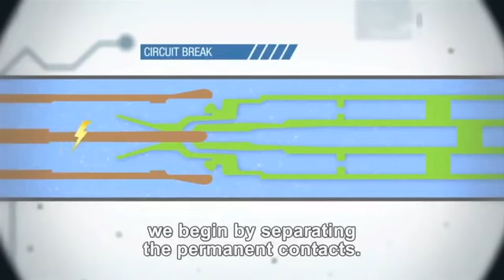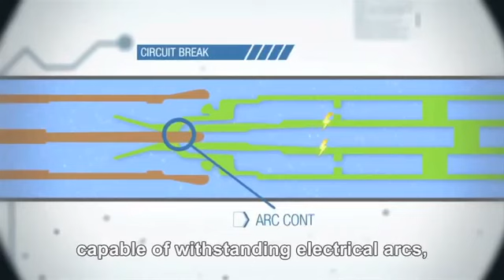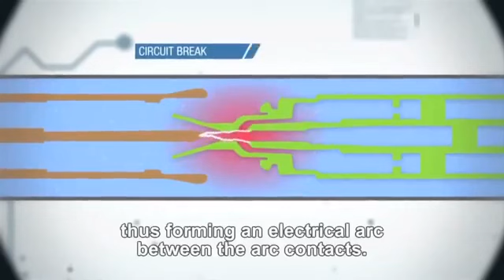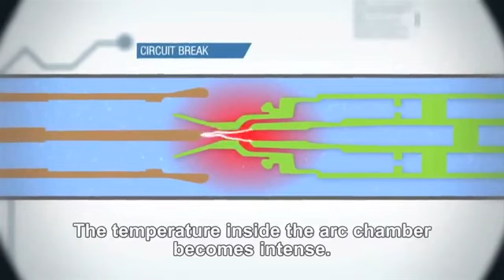In the case of a circuit break, we begin by separating the permanent contacts. The current then concentrates in the contacts situated at the center of the arc chamber. Composed of more solid material, capable of withstanding electrical arcs, they are called arc contacts. The central contacts separate, thus forming an electrical arc between the arc contacts. The temperature inside the arc chamber becomes intense. The gas molecules explode, and the SF6 loses its insulating qualities.